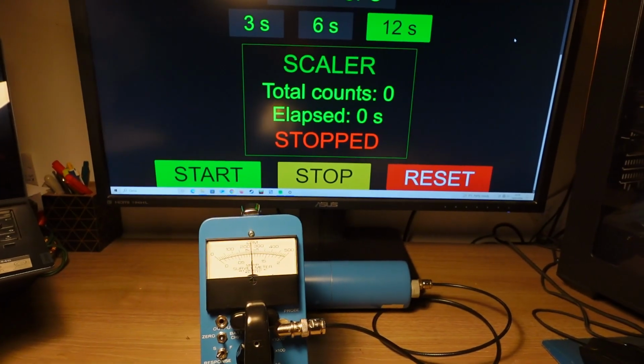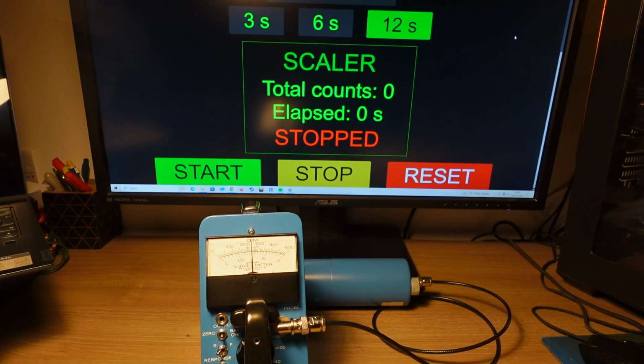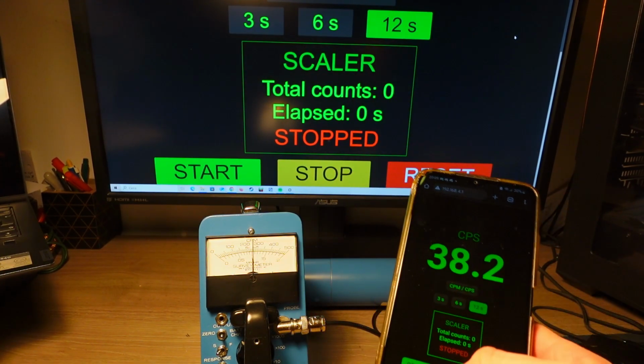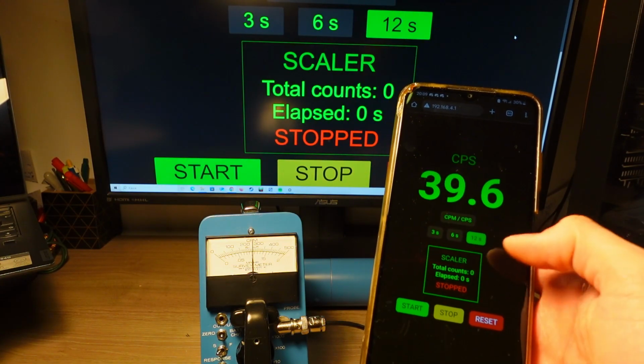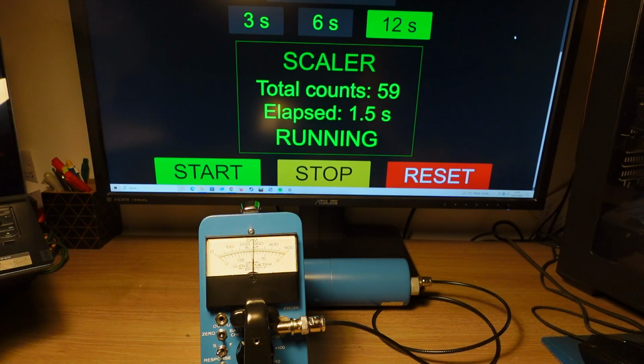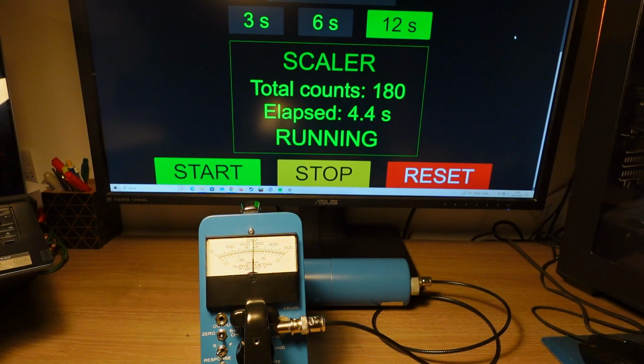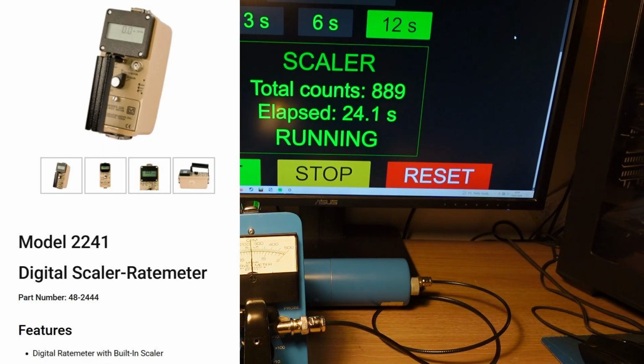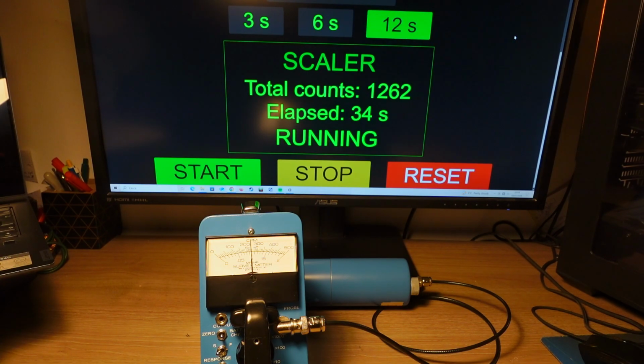We can see that we can use it as a scaler or a ratemeter. So here on the phone, but this works also on the computer, we can, for example, press start, and as you can see, the scaler starts counting. This is now live counting exactly every single pulse that the meter is receiving from the probe and adding it up to the previous one. And why is this important? This is an important capability that usually only more expensive meters have, and it's important because with the right probe it allows you to check for contamination, for having a more precise measurement.